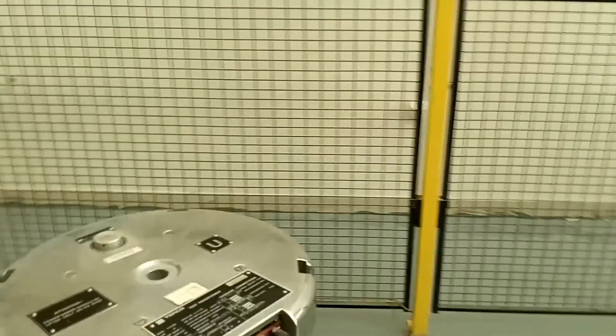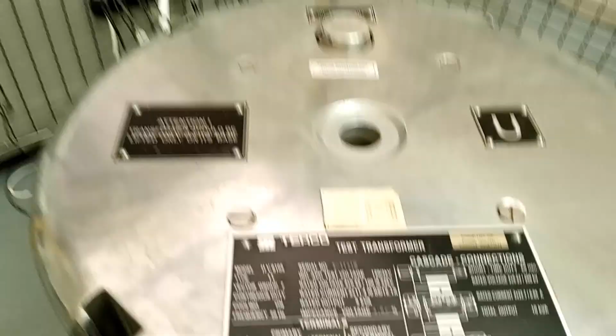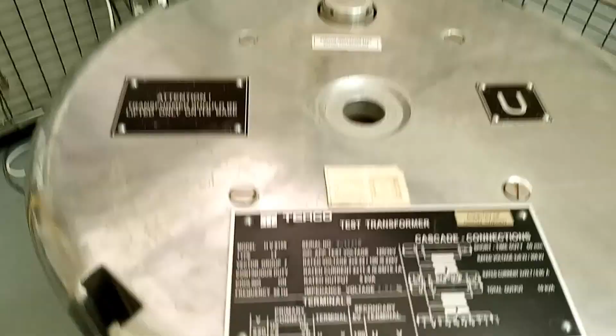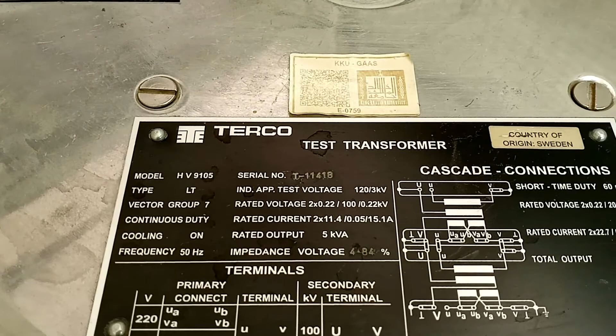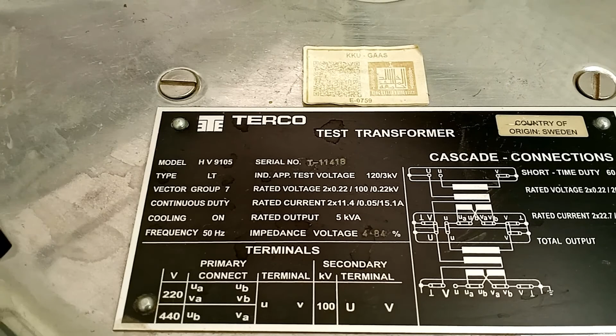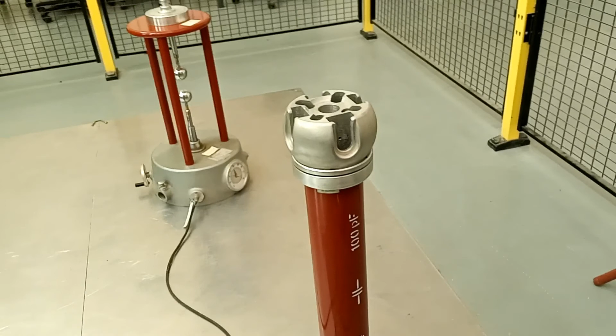The step-up transformer we are using here is a 5 kVA transformer. If you check the rating here, it can step up from 220 volts to 100 kilovolts. To measure this secondary output from the transformer, we are using a measuring capacitor which can withstand up to 100 kilovolts, whose capacitance value is 100 picofarad.